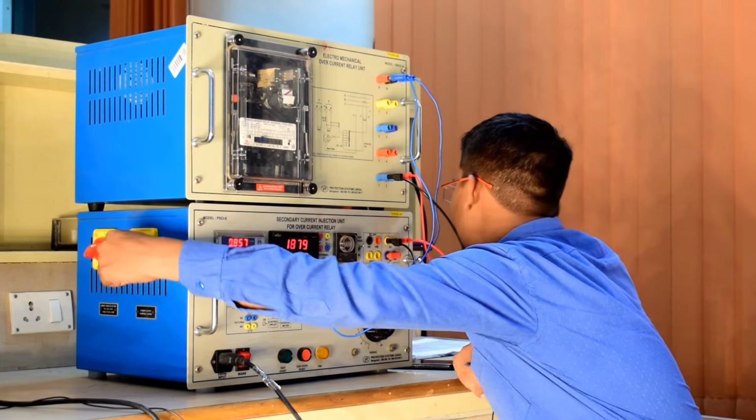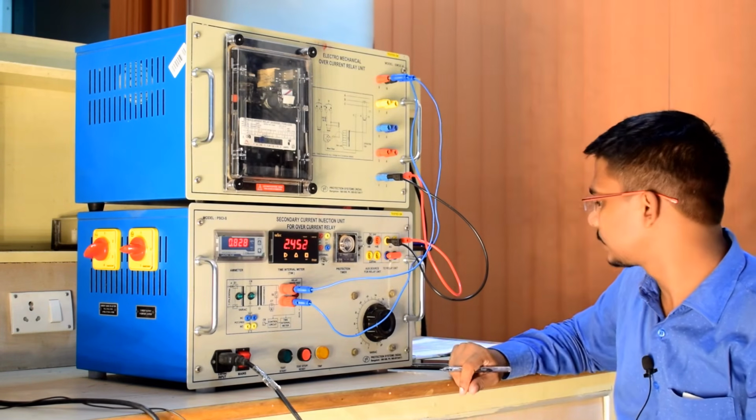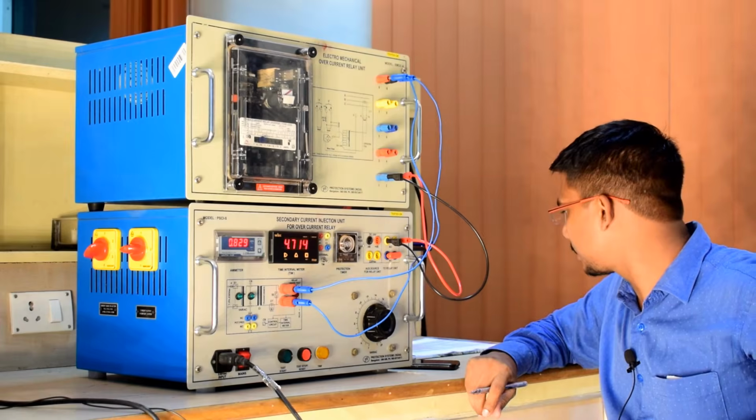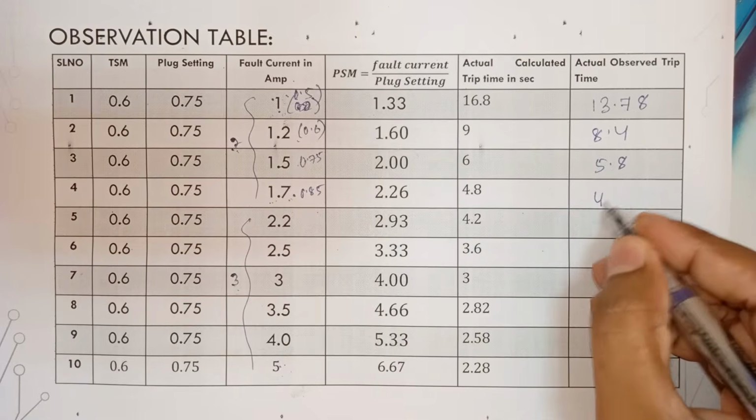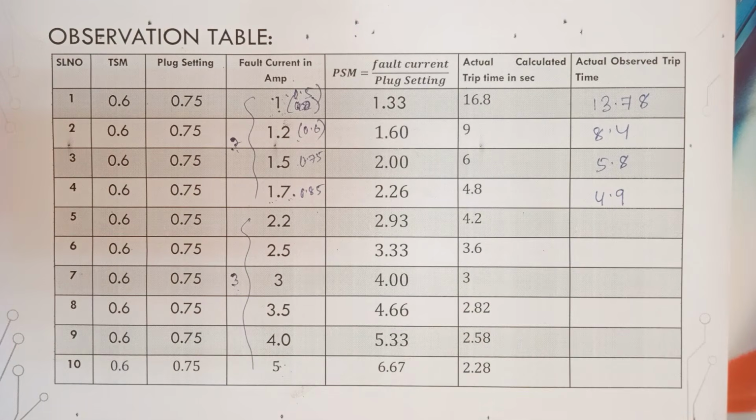Now you will see the time. Our expected time for this current is 4.8 seconds, and we got 4.9 seconds. So exactly similar.